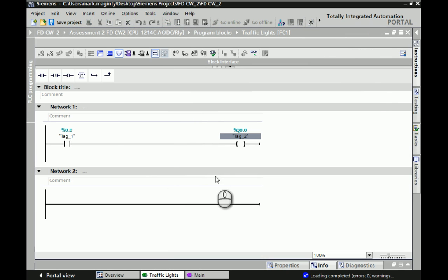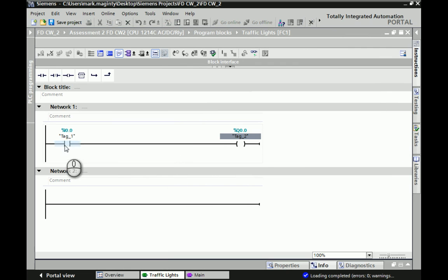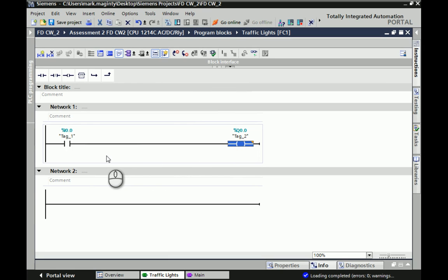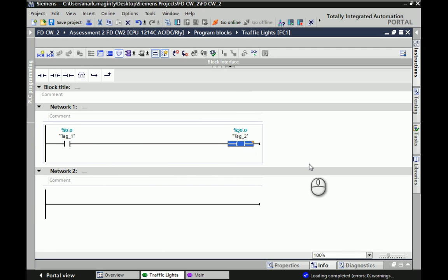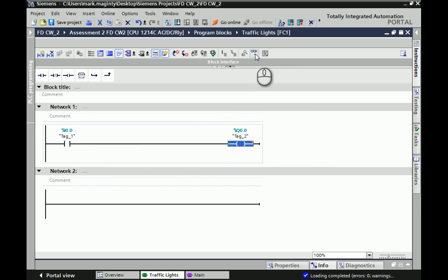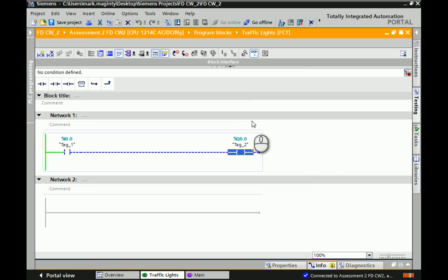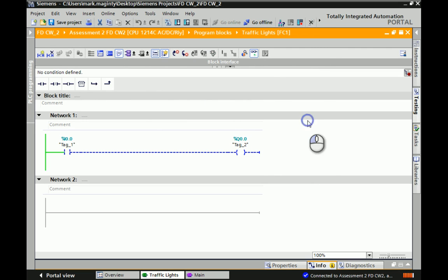So we're now looking at FC1. This is the particular function that I've decided to load. I've done a very simple inline, one input and, basically. This input one, or I0.0, when activated will turn on Q0.0. What we're able to do is not only test that it's actually downloaded, but we're actually able to test and see it live running. What we need to do is, if you go up to the option here, within FC1 itself, there's a monitor on or off mode. If you click the monitor mode here, it will take a few seconds for it to load.